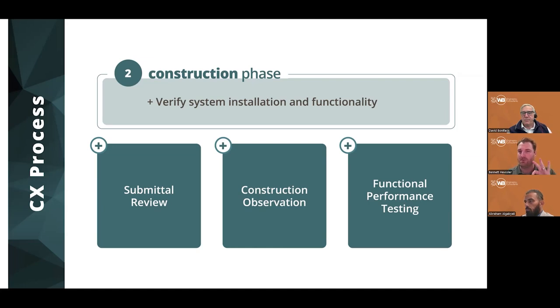In my mind, there are three main things you find in commissioning. One is anything energy efficiency related, like not having a valve run or open when it doesn't need to, and you can capture that. The other is safety and resiliency, like with the generator, making sure stuff will fail correctly. And the third, which is a good segue to the warranty phase, is operational effectiveness, making the system easy to run for the building operator.